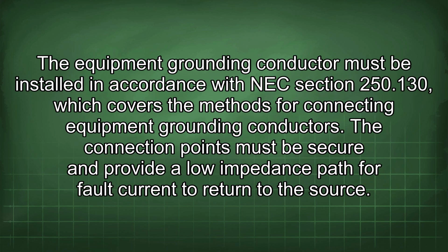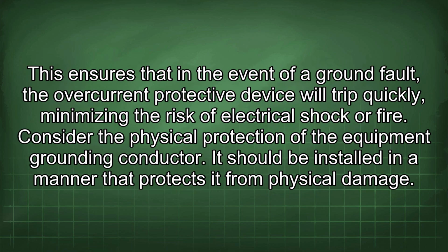The equipment grounding conductor must be installed in accordance with NEC section 250.130, which covers the methods for connecting equipment grounding conductors. The connection points must be secure and provide a low impedance path for fault current to return to the source. This ensures that in the event of a ground fault, the overcurrent protective device will trip quickly, minimizing the risk of electrical shock or fire.